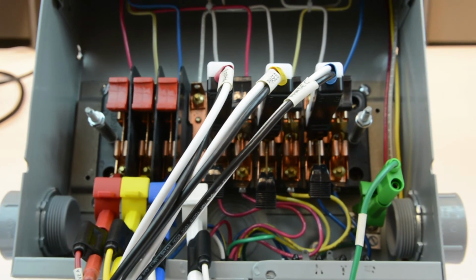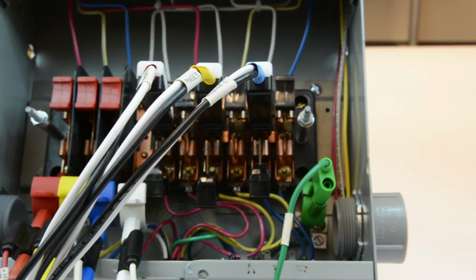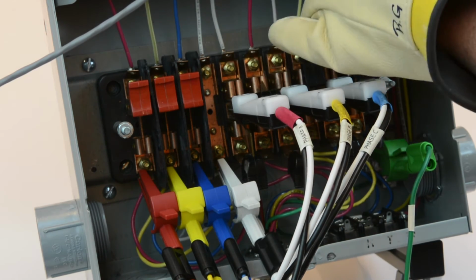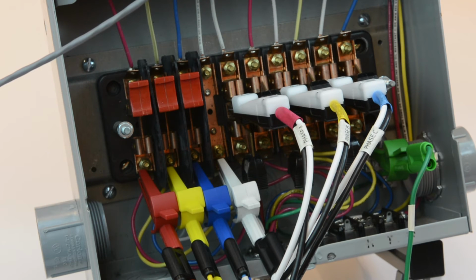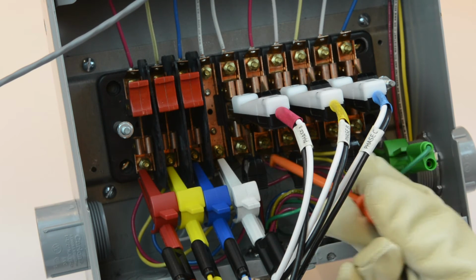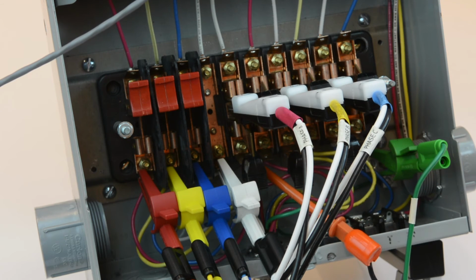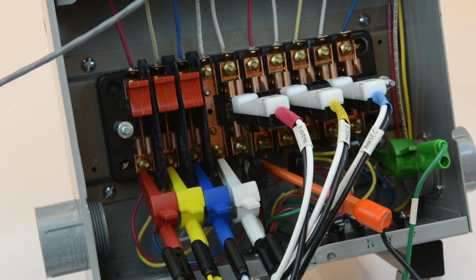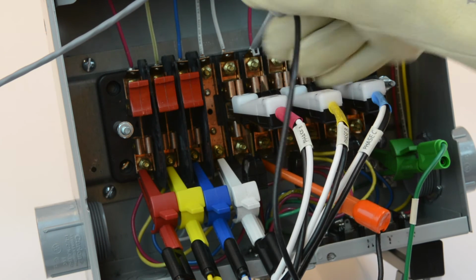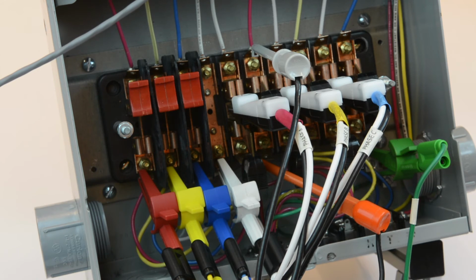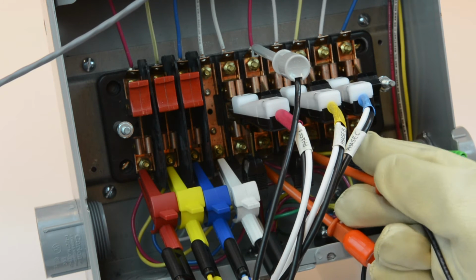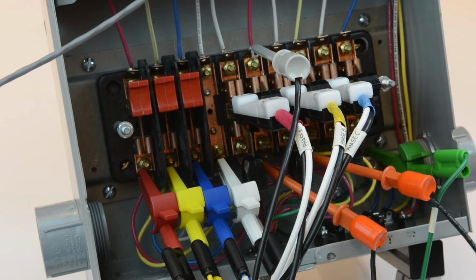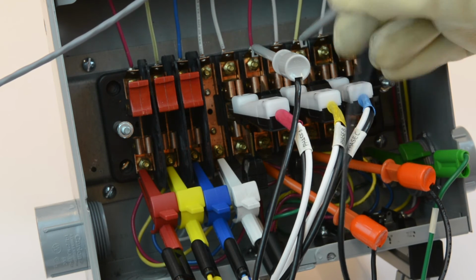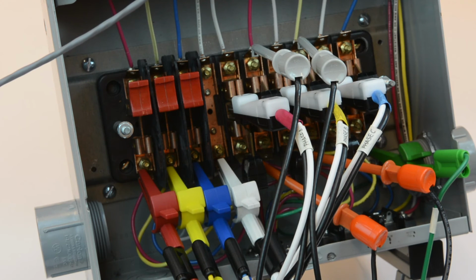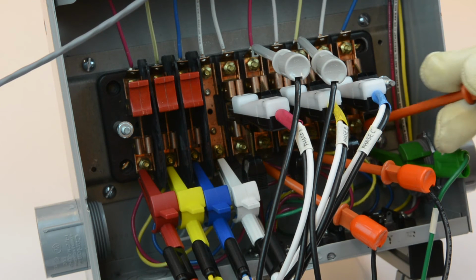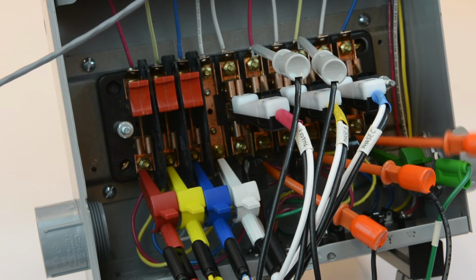To prepare for the phantom load test, the current circuit must be isolated. To shunt the CTs, connect the jumper cable from the top of the drive CT test switch to the bottom of the same phase return. Repeat this process for each of the other phases. Once your connections are made, press F6.